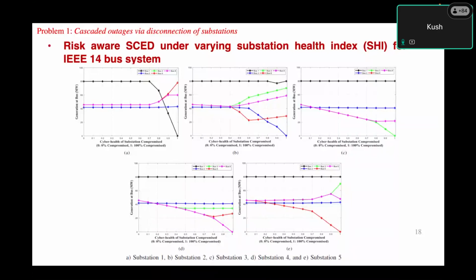By 0, it means it is not compromised at all. As we reach a certain level, we gradually decrease the generation at bus number 1. Why? Because there is a persistent threat at substation 1, and we don't want the generators there to generate more power. We don't want to be dependent on them, so we decrease their generation and ramp up the other generators at the other buses to meet the system demand. So this is how the risk-aware security constrained economic dispatch may work if we include the substation health index within the formulation.